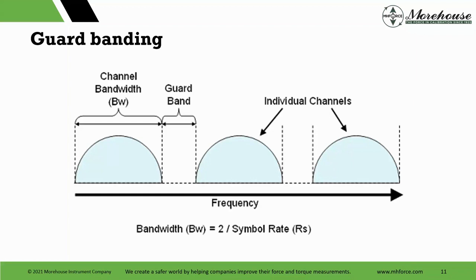So if you choose not to account for measurement uncertainty, or ignore measurement uncertainty, you still made a choice, and you might have a very, very high level of risk if you're making that choice. Or you may not understand what shared risk means or what simple acceptance really means. But that's as far as guard banding, early radio days. And what we're doing with uncertainty, we're doing the same thing. We're saying, let's use a method to ensure our risk level does not exceed X.